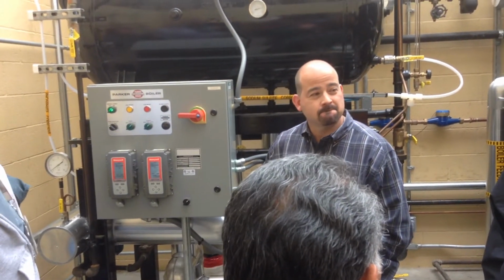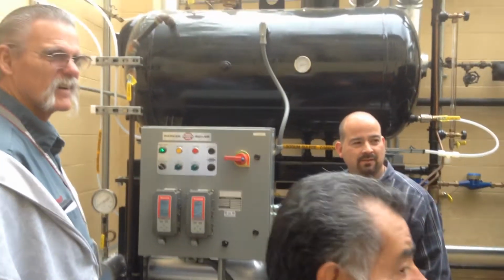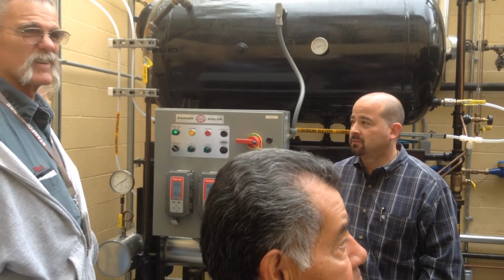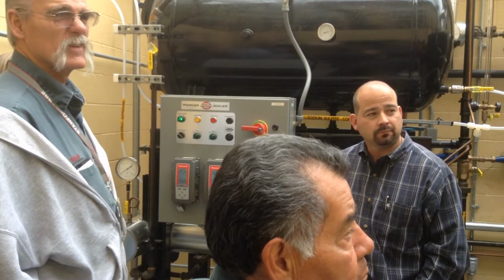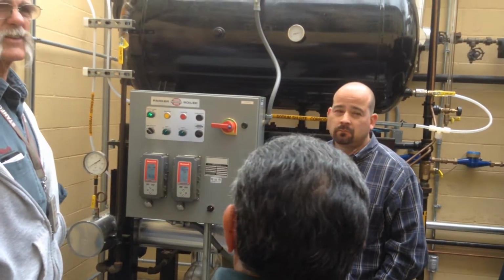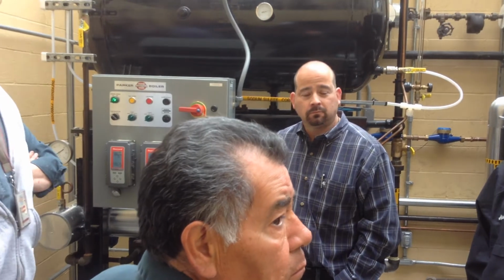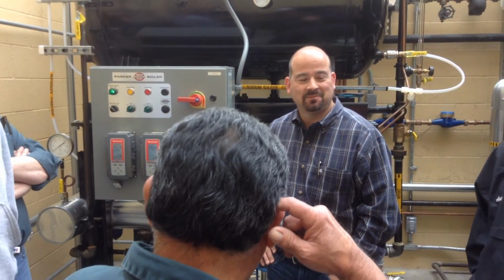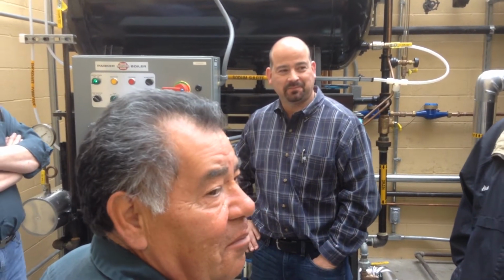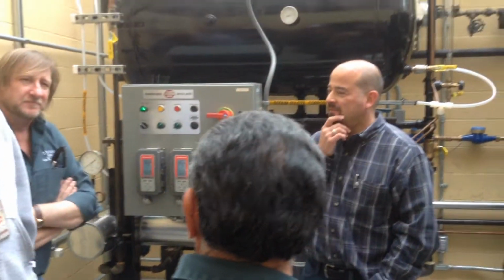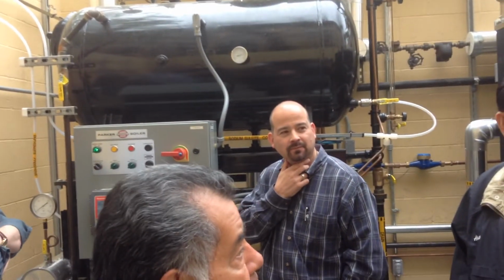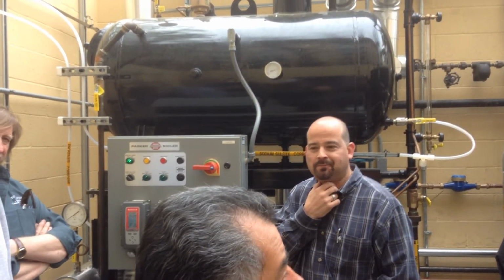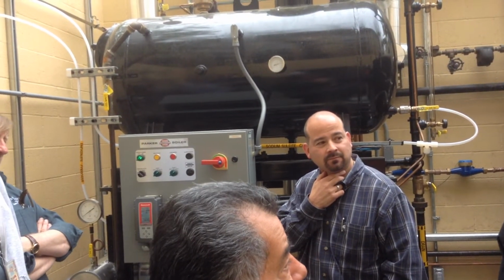Now my big question is, I've got the plumbers as the call-out. Who's going to be the call-out, now that I see all you guys here? Because when this thing fails, are you guys going to get called out, or the plumbing shop? If there's a water leak, the plumber. It's usually the controls. I don't have a leak. So that's going to be a general. Don't call a plumber. Call the HVAC shop, and if there is a leak, then they'll call the plumbing shop. Right now I have them installed as the call-out, so I'll change that to HVAC. Yeah, the boiler is out, not plumber, because there is no leak. If we call the plumber and they call us, then we have two guys come out.